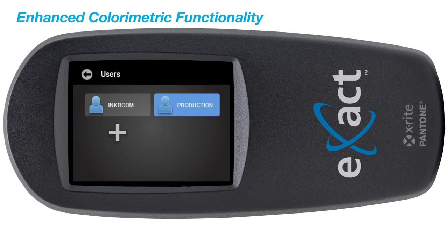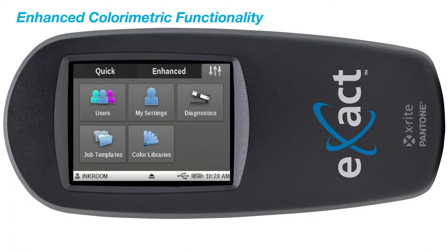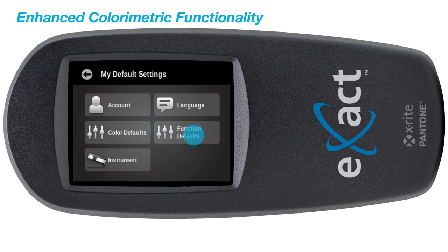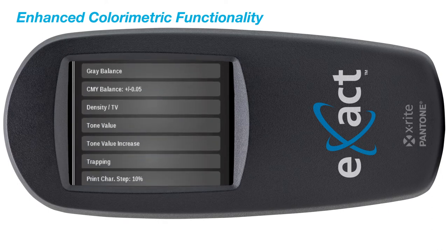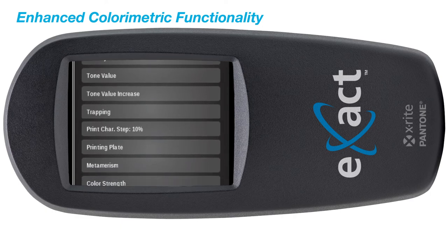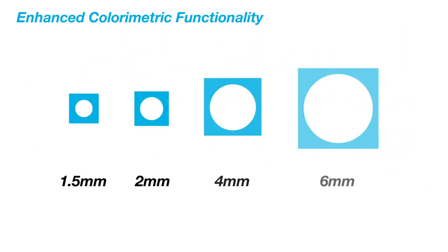The Exact Advanced is the most configurable instrument on the market by: 1) offering multiple advanced user profile capabilities allowing you to configure your device for multiple user profiles and different configurations; 2) driving workflow confidence for each job as tools can be locked and customized; 3) providing a full range of aperture sizes to provide job flexibility as your business needs change; and finally, providing substrate analysis capabilities with the brightener index function.